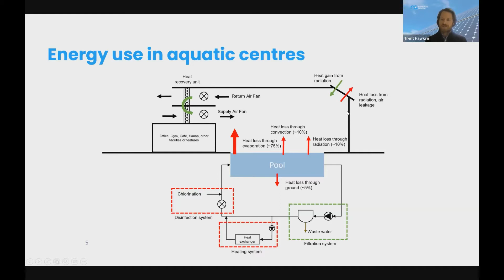In the pool itself, there are a range of areas where heat is lost—through the ground, direct radiation, convection into the air, but mostly through evaporation off the pool surface. As Alan alluded to, you also have to actively condition that space: removing air and bringing in fresh air, cooling or heating it depending on the season—usually cooling—and dehumidifying it as well. There's also heat loss through glass and other building fabric.